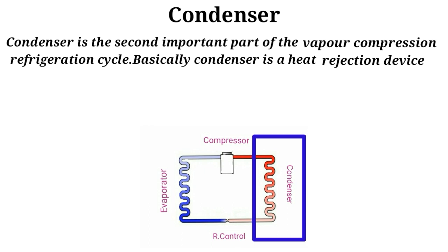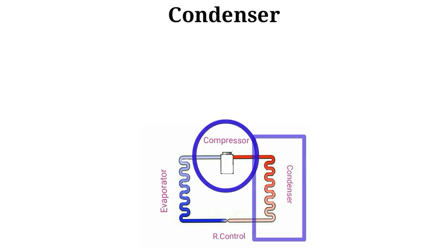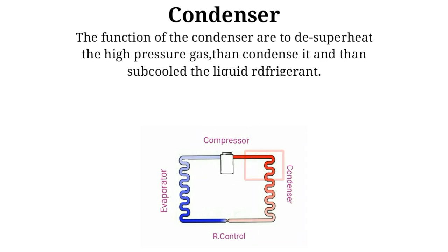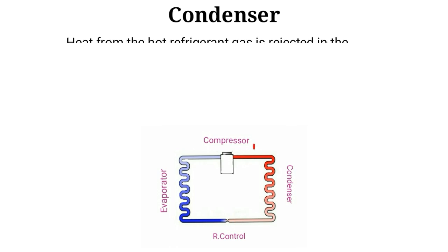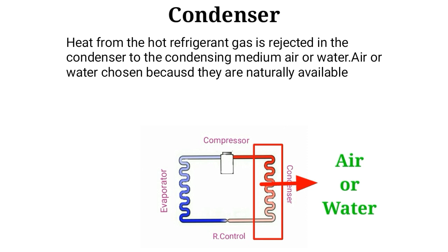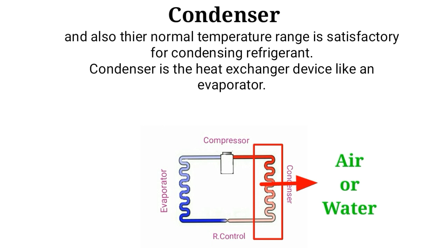The condenser is a heat rejection device which is installed after the compressor in the vapor refrigeration cycle. The functions of the condenser are to desuperheat the high pressure gas, then condense it and then subcool the liquid refrigerant. Heat from the hot refrigerant gas is rejected in the condenser to the condensing medium — air or water — which are naturally available and have a satisfactory normal temperature range for condensing refrigerants.